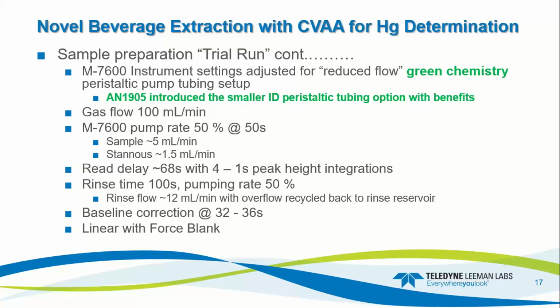Read delay was 68 seconds. I'm doing 4 integrations at 1 second each on peak height. Rinse time was 100 seconds with the rinse pump set to 50%. The rinse flow is about 12 milliliters per minute, but I recycled back to the rinse reservoir, so very little is consumed. And then a baseline correction point. I only used a single front end baseline correction point, set at 32 to approximately 36 seconds. And for the line, I used linear with force through blank.